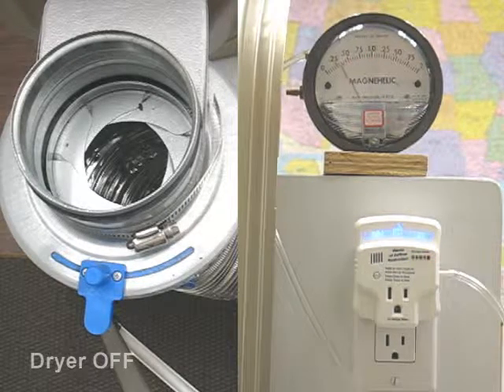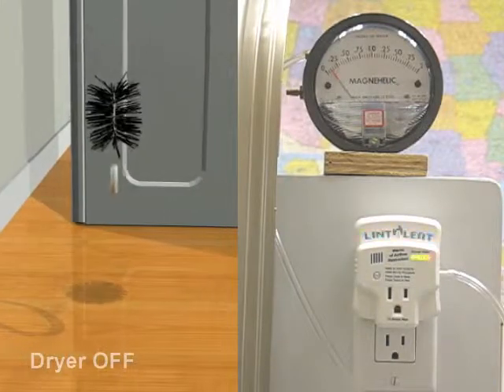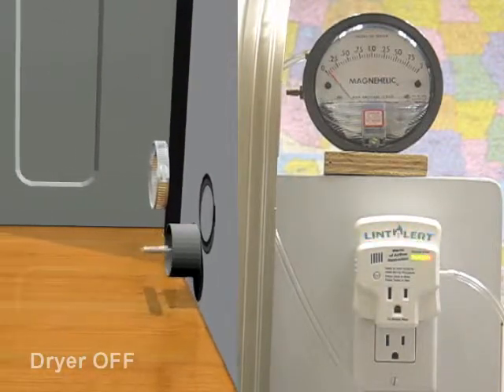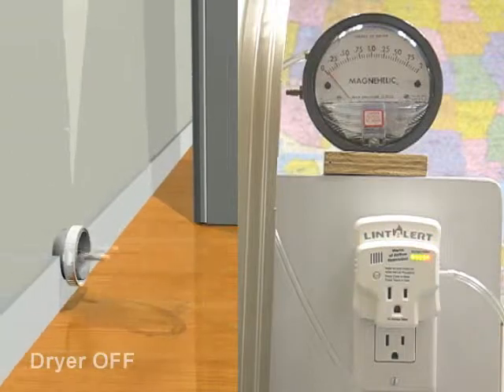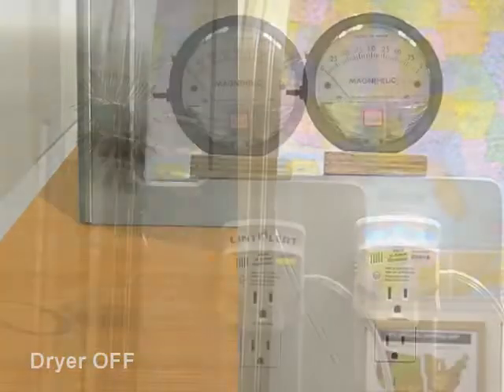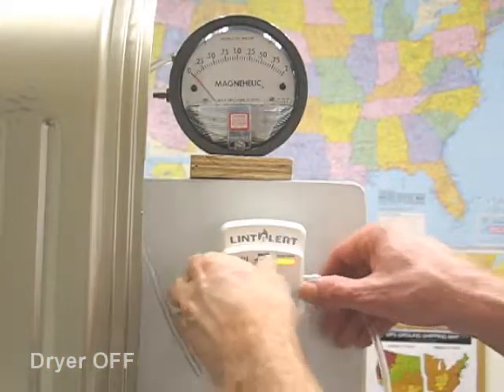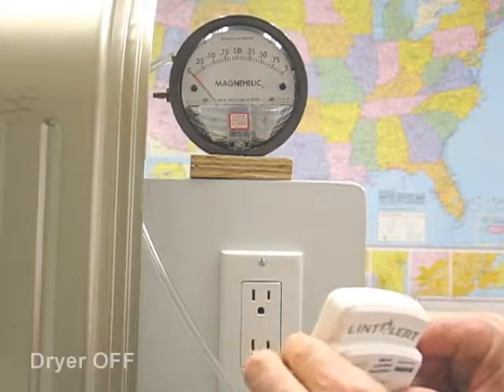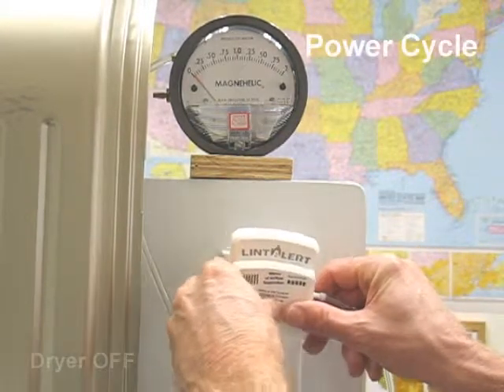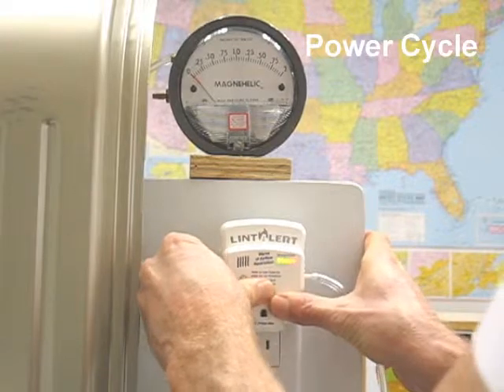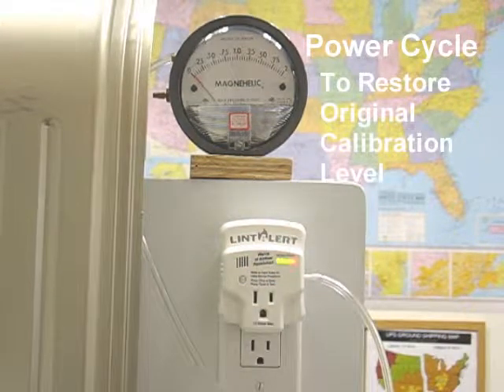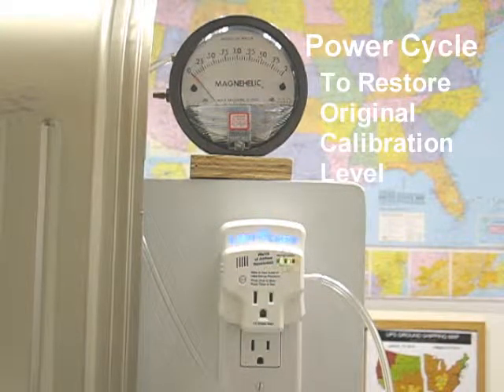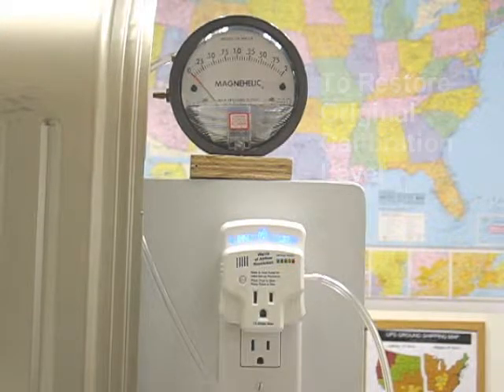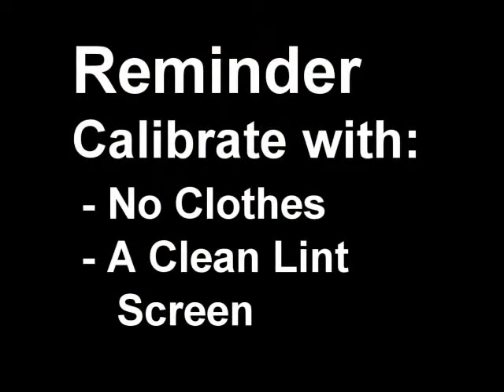Once the back pressure has been relieved, most likely accomplished by cleaning out the exhaust conduit or termination hood, the LintAlert can be recalibrated. If the alarm state was accidental, perhaps the kids were interfering with the termination hood, simply power cycle the LintAlert. Remember to calibrate with no clothes in the drum and with a clean lint screen.